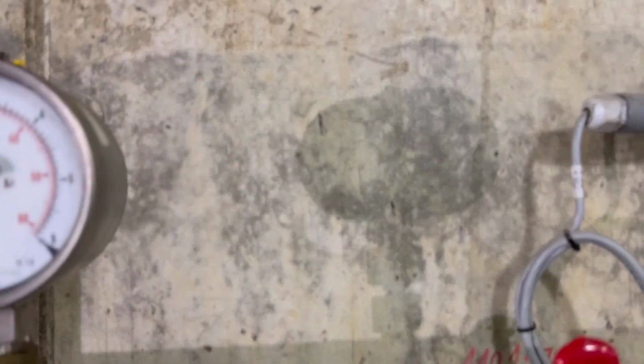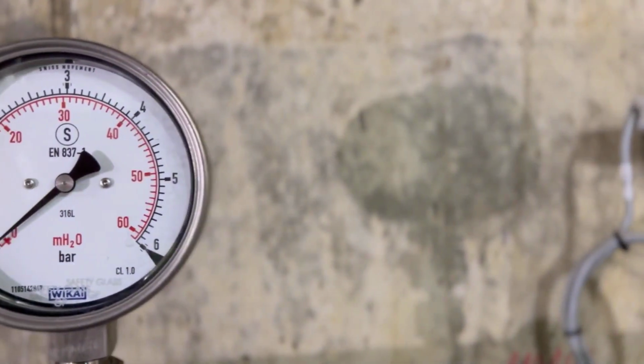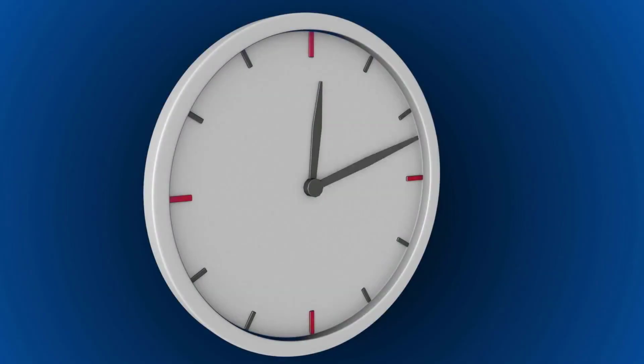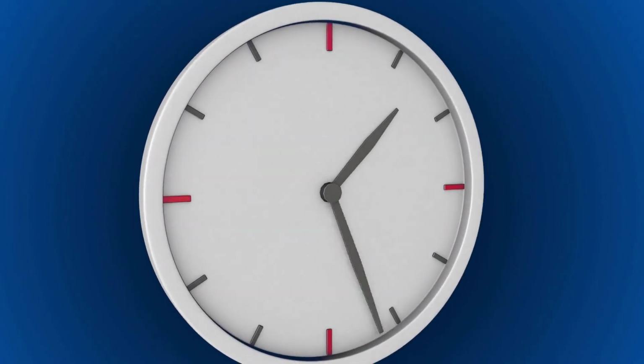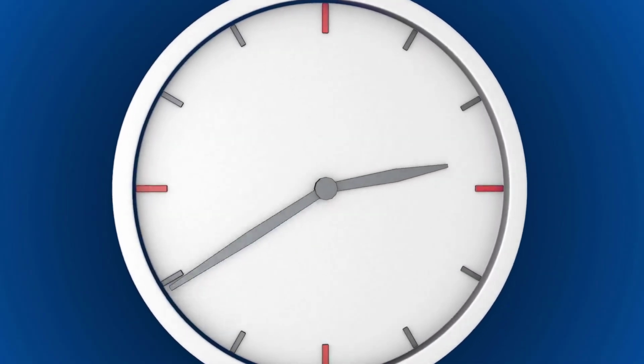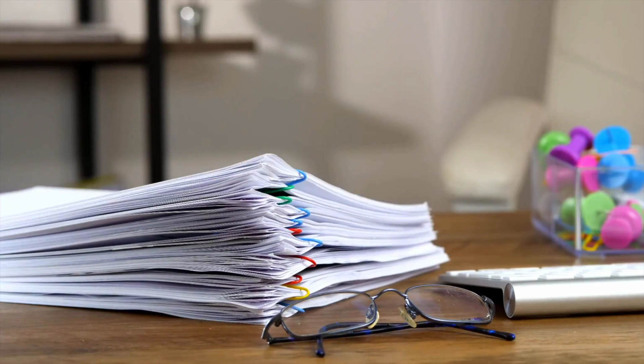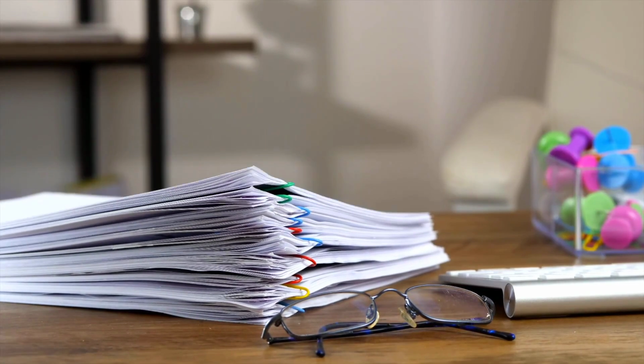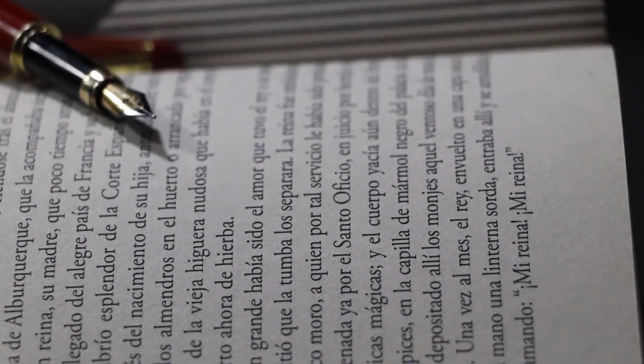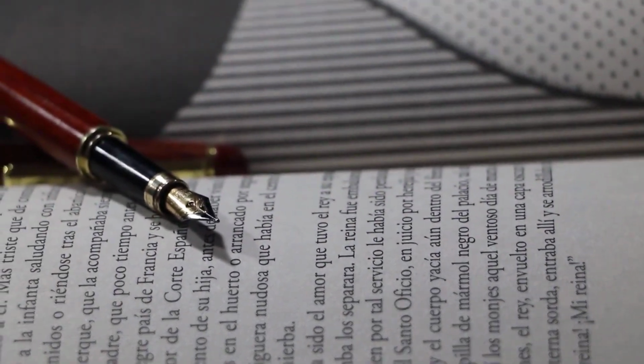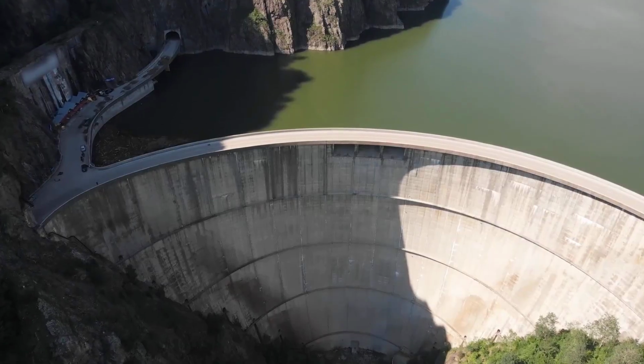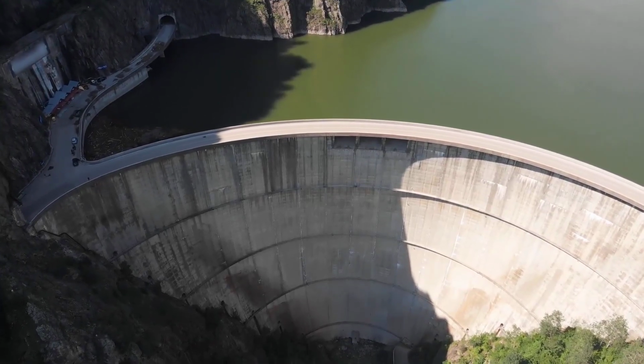That is the lesson, and it is a narrower one than it first appears. Nobody at Sayano-Shushenskaya was missing information. The vibration of Unit 2 was measured, logged, and reported for 4 months as it climbed past the manufacturer's limit and kept going. The failure was not that the machine gave no warning. It was that the warning had nowhere to go except a filing cabinet. A measurement that cannot stop a machine is not a safety system. It is a record of how the accident happened, written in advance.